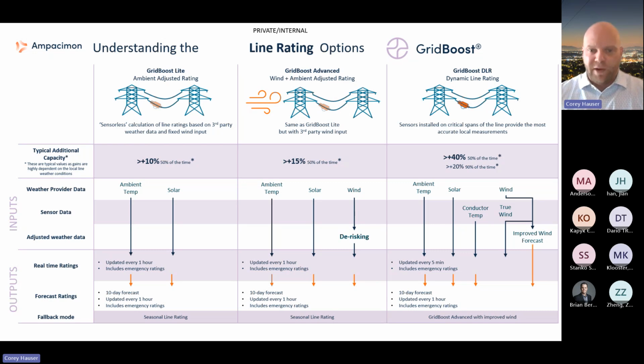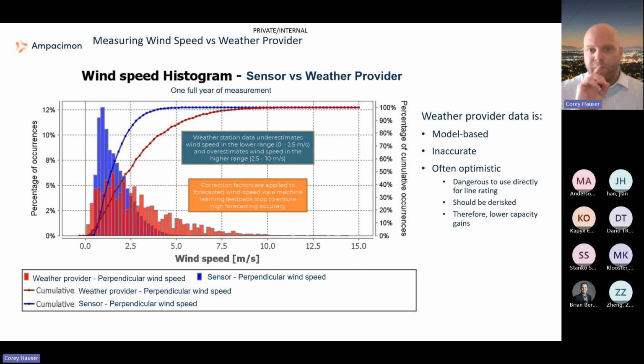We also have an improved wind forecasting here. So typically when we talk wind, we don't suggest having forecast more than 3 days in the future just because it's so variable. But with our solution, we are able to increase the accuracy of those forecasts. And we are able to do that by comparing our sensor measured data versus third-party weather data over time and creating correction factors. So as we factor those in and determine the misses, call it, in the past compared to what is actually happening on the line, there are correction factors applied and algorithms applied that allow for a more accurate forecast. So overall, these are our three line rating options, both sensorless and sensor-based, and we can jump into these a little bit further.